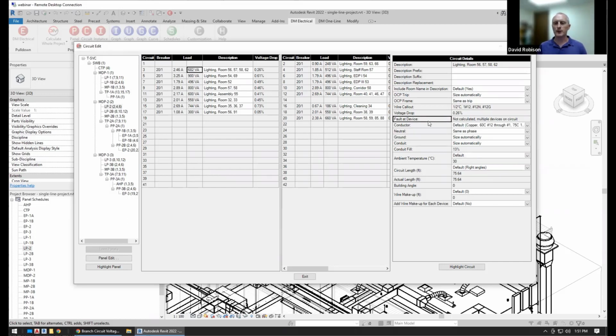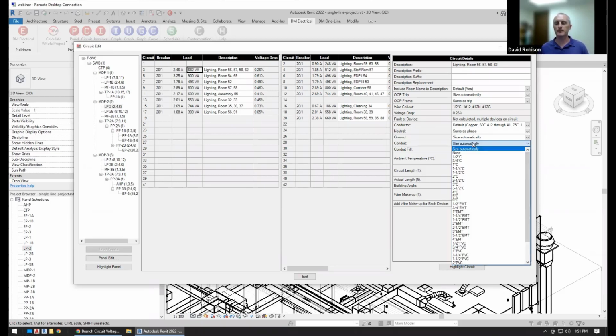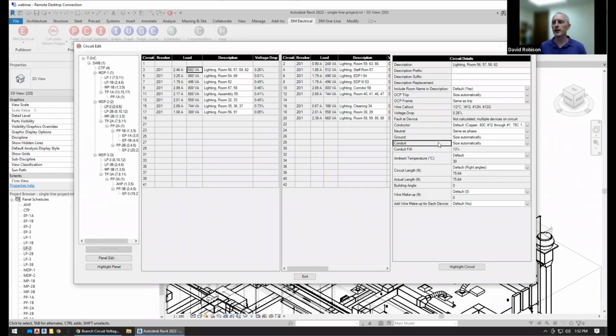I'm going to finish out the conduits, and then we'll take a look at the conductor question I've got. So for the conduit, we can size it automatically, and it's going to give you a 40% fill. So we'll take a look at the wires, and we'll make sure that we don't exceed a 40% fill. You can set it to none, or you can set a specific size if you want to. And then there's a question, can we set a minimum size where we don't want to use anything less than 3/4 of an inch, which is the most common request, which comes up all the time. A lot of people don't actually like to use 1/2-inch conduit.